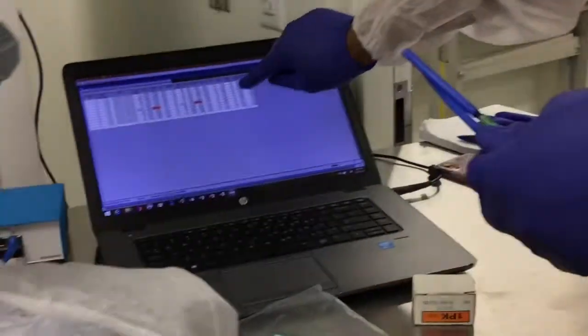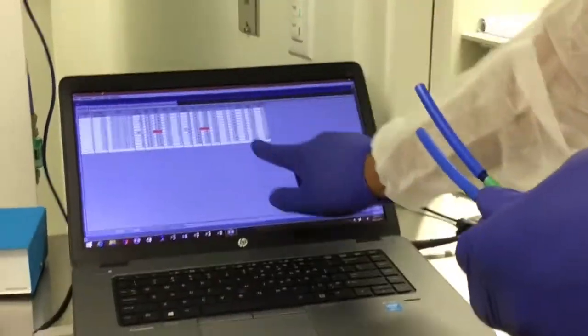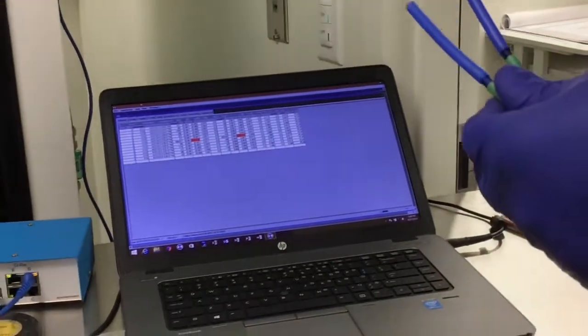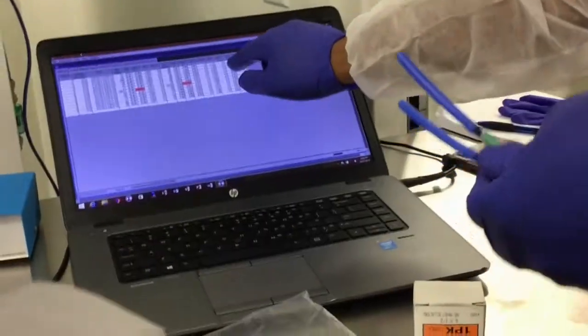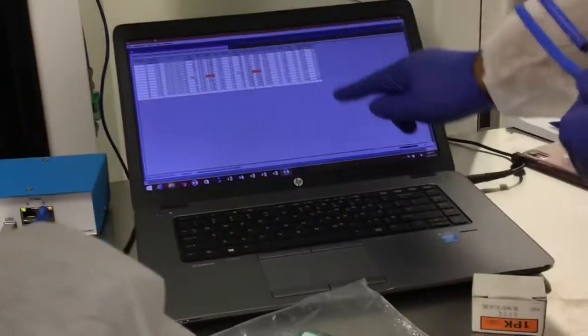So now, this is the metabolic window. The flows, again, are regulated to be around 0.9, but guess what? They should always be within 2%. If not, they turn red. So cage 1, you see those things, it's the same thing here. They make them, but they cannot make a million of them to be exactly the same. The hole in it is made by a little needle, and any time it makes a hole, it is different from the next. So they just should be within a specific range. Since we use these actual numbers to do the calculation, it really doesn't matter, because we measure it at the flow control. So we want 0.9, but you get cage 1 at 0.913, cage 2 at 0.907, as long as they are within 2% of each other. And if they are not, they will turn red.